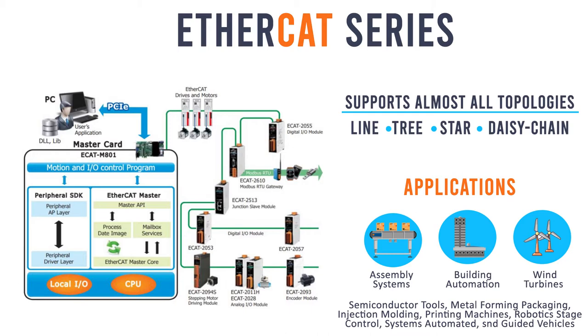Up to 65,535 devices can be connected to EtherCAT, so network expansion is virtually unlimited. It offers a lot of flexibility regarding cable types, so inexpensive industrial Ethernet cables can be used between two nodes up to 100 meters apart in 100BASE-TX mode.